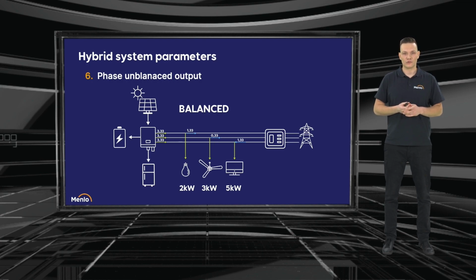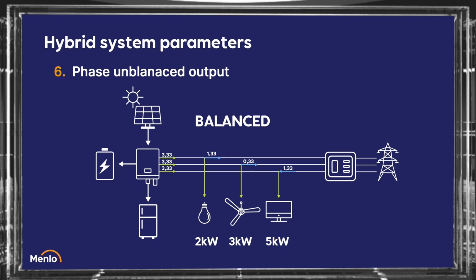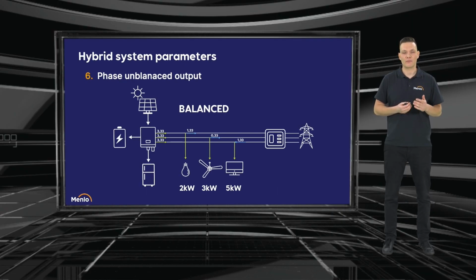Then we have phase unbalanced output, so the amount of energy that the inverter produces per phase. Here on the graph we show a balanced output. The loads in total take 10 kilowatts, 2, 3, and 5 respectively on each phase. But because the inverter has a balanced output, it puts one third of this demand power on each phase, so 3.33. What it means is that on the first two phases it will produce more energy and feed it into the grid, and on the third phase it will take from the grid. This is a problem if you sell energy at a lower price than you buy it, because it's not profitable for you. That's where the unbalanced system comes in.